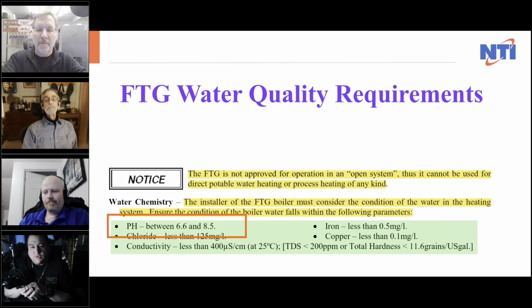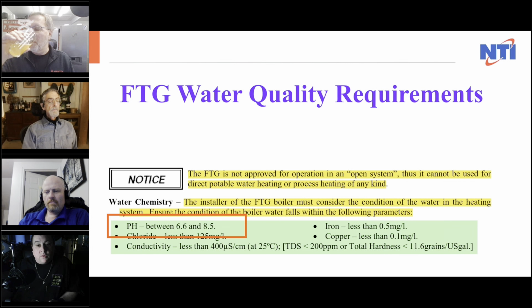When I show you test results from a job I visited, you'll understand what pH and excessive oxygen will do to a system. If you're getting a lot of oxygen in the system from a lot of makeup water, that's when you may want to talk to the consumer—or if it's a commercial application, the property manager or business owner—and say, we've got something going on in the system, we need to cure it.